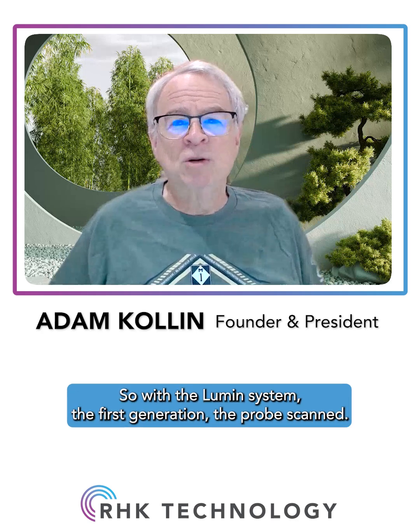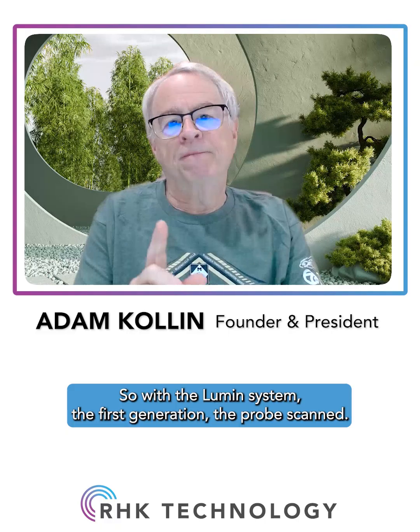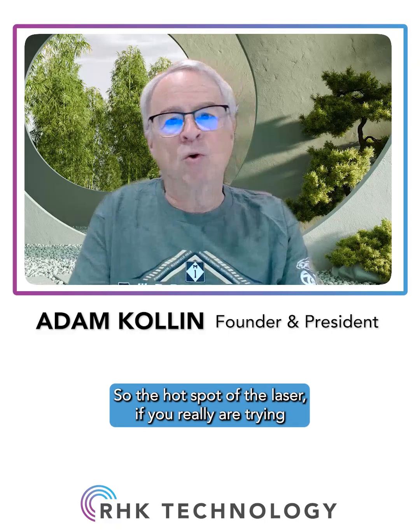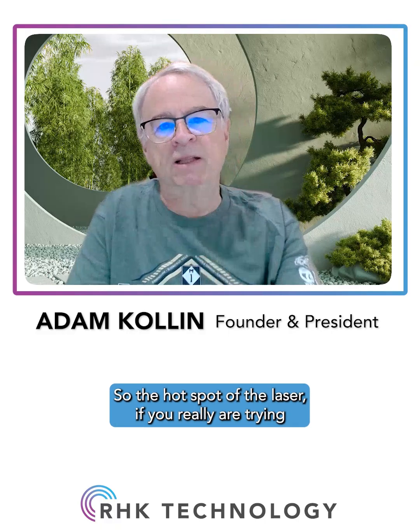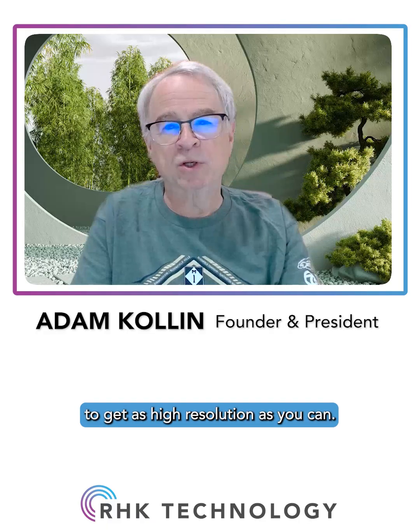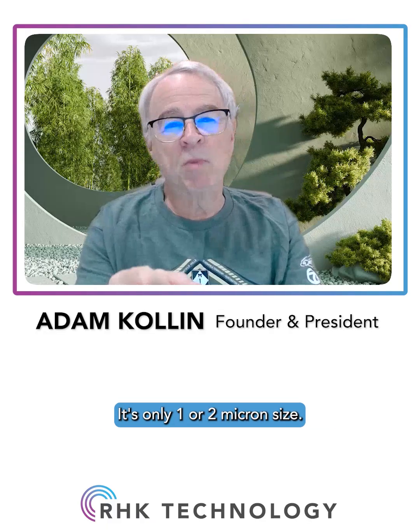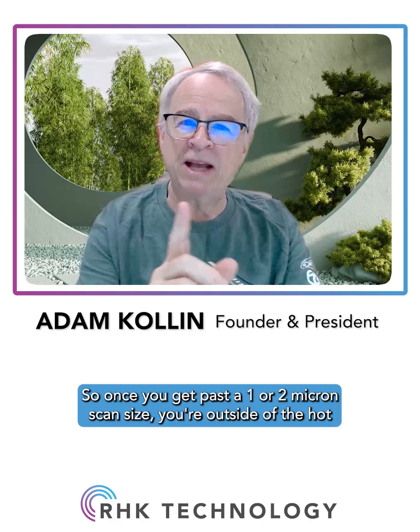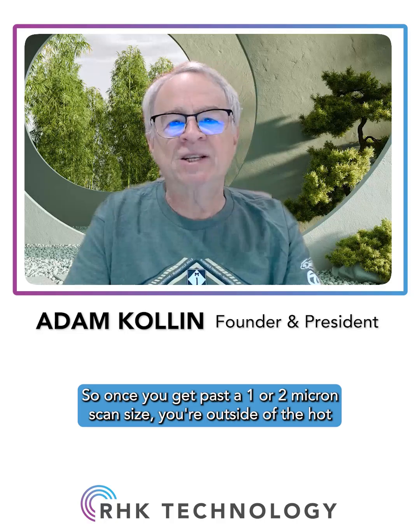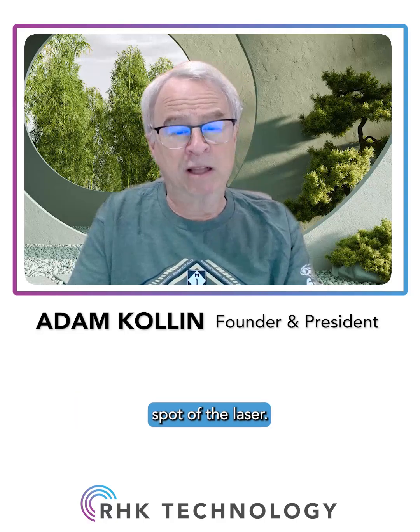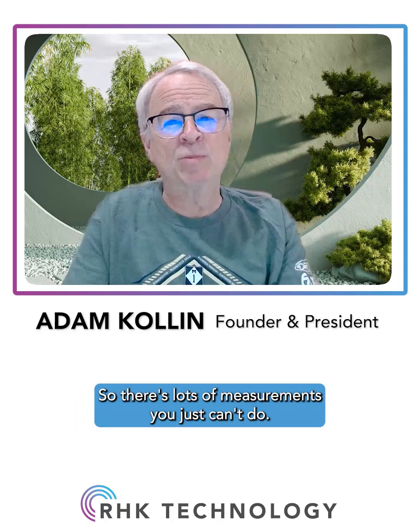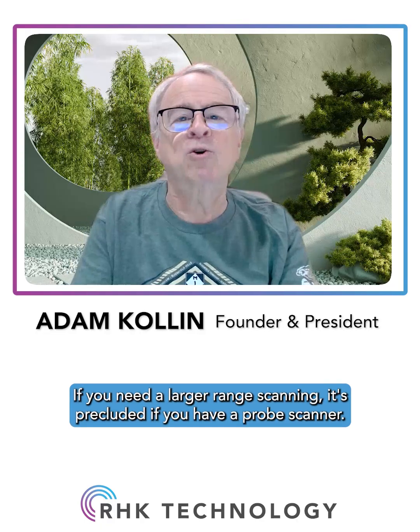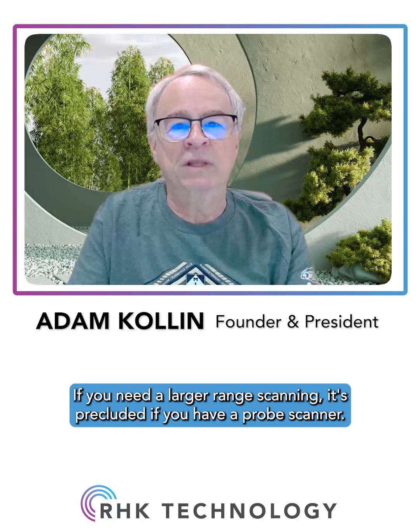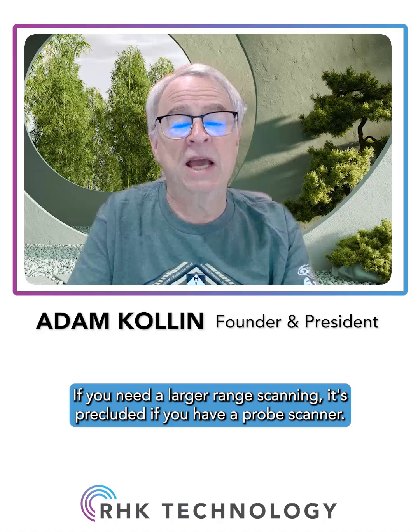So with the Lumin system, the first generation, the probe scanned. So the hot spot of the laser, if you really are trying to get as high resolution as you can, it's only 1 or 2 micron size. So once you get past a 1 or 2 micron scan size, you're outside of the hot spot of the laser. So there's lots of measurements you just can't do. If you need a larger range scanning, it's precluded if you have a probe scanner.